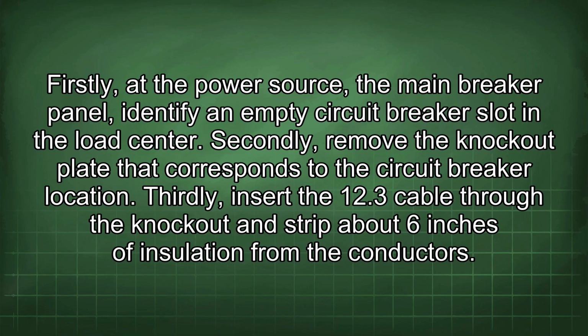Firstly, at the power source, the main breaker panel, identify an empty circuit breaker slot in the load center. Secondly, remove the knockout plate that corresponds to the circuit breaker location. Thirdly, insert the 12-3 cable through the knockout and strip about 6 inches of insulation from the conductors.